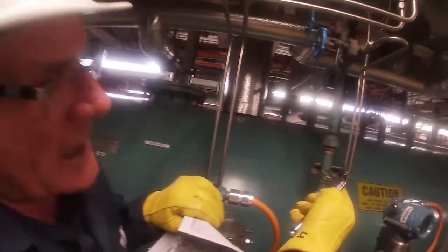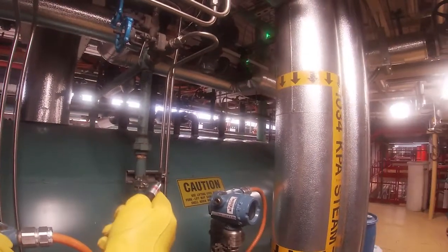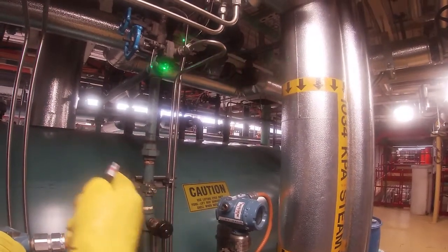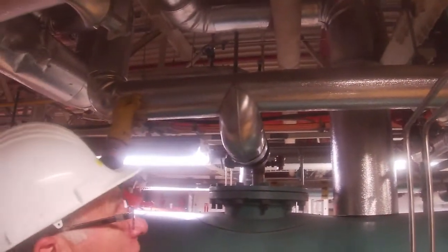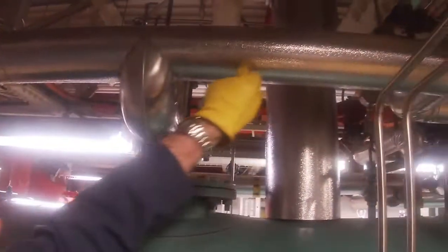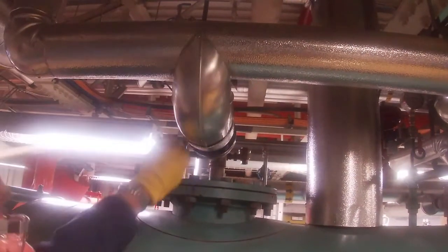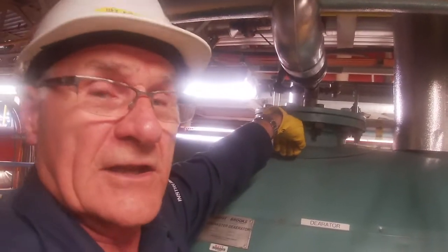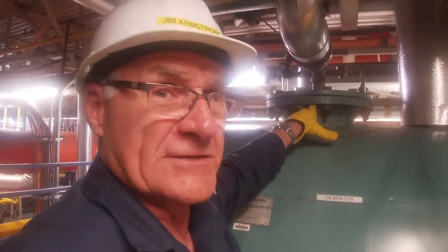We've got a block valve there that we would have to open before startup, and from there it gets added into the condensate stream. The condensate from the hot well is coming this way. Any fresh water makeup we need comes that way. They join together and go down into the deaerator vessel and through the spray nozzle. Okay?